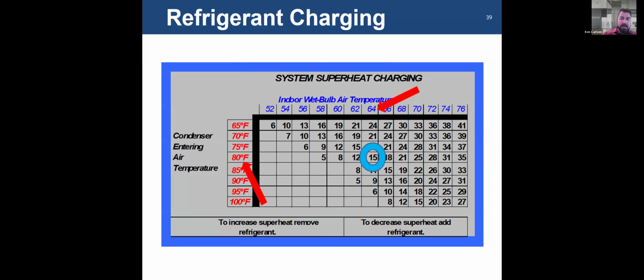Going the other direction, if you measured 35 for whatever reason, and these were your pressures, if your pressure was 130 and you were measuring 40, you would be in subcooling, right? So if you're in cooling mode and you're on the discharge side, typically your pressures would be much higher. You'd be much more like 254, 274, and then you would calculate your subcooling from there. We'll talk about that in a few slides.